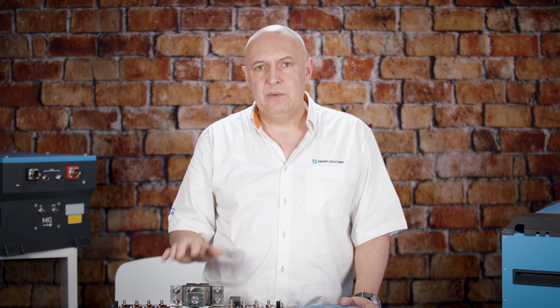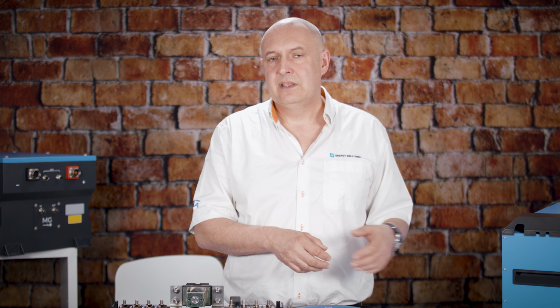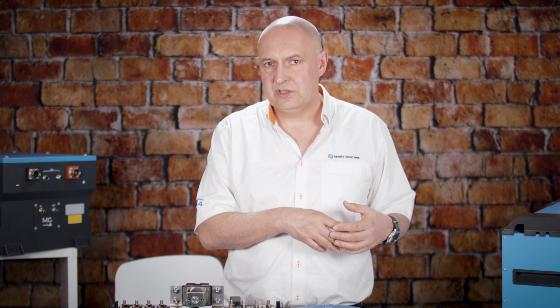Sometimes that's just to create a bit of redundancy, so that if we have an issue with one set of batteries or one BMS, we can keep the system live with a duplicate or parallel system. Where we're doing that, it's in principle just a matter of splitting your batteries across the 2 BMSs and combining the output of those 2 BMSs together to provide a single supply to your consumers or charging sources. The slight complication is really how we deal with the data and how we deal with the volt-free contacts and signals that I discussed earlier, where we're trying to control charging sources. So now we've got 2 dry contacts that are in parallel, or we've got 2 13.5 volt outputs, and we need to respond to either or both of those.